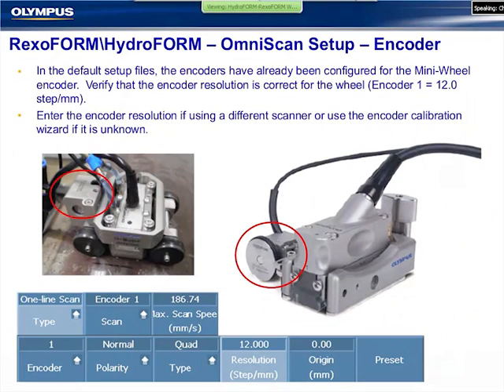So our encoder setup now, either using the HydroFORM water version or the RexoFORM Rexolite, in the one-line scan configuration, we need to enable one encoder and determine that encoder as the scan axis. The OmniScan MX2 has a two-axis input. So the software will determine our maximum scan speed.